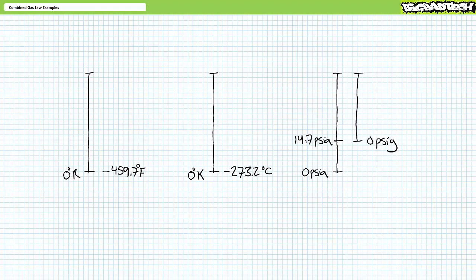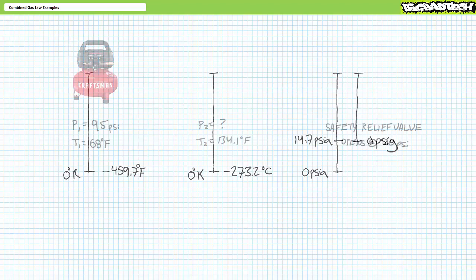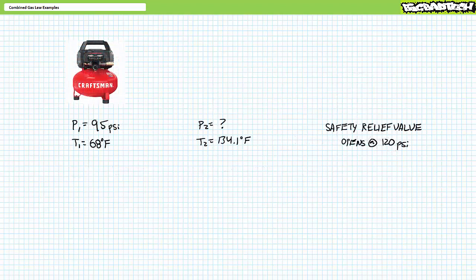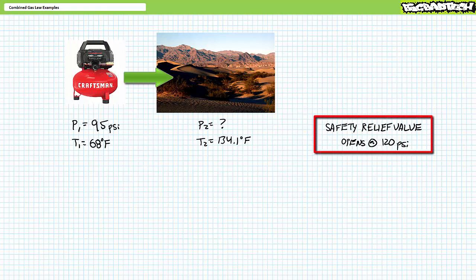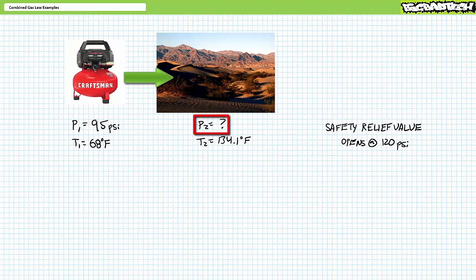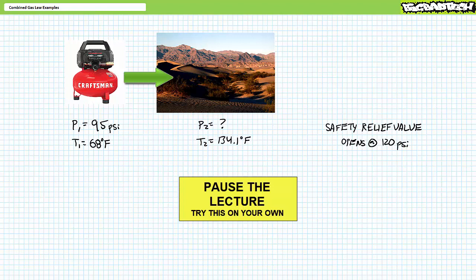This concludes the brief review. Let's begin with the illustrated examples. Problem one: consider a rigid metal receiver pressurized to 95 psi in a 68-degree Fahrenheit workshop, then brought to a job site at Furnace Creek Ranch in Death Valley, California, and left in the hot sun, reaching a temperature of 134.1 degrees Fahrenheit. The safety relief valve opens at exactly 120 psi. Does it blow? Determine the pressure in the receiver at the elevated temperature, presuming the volume of the rigid metal receiver remains constant.